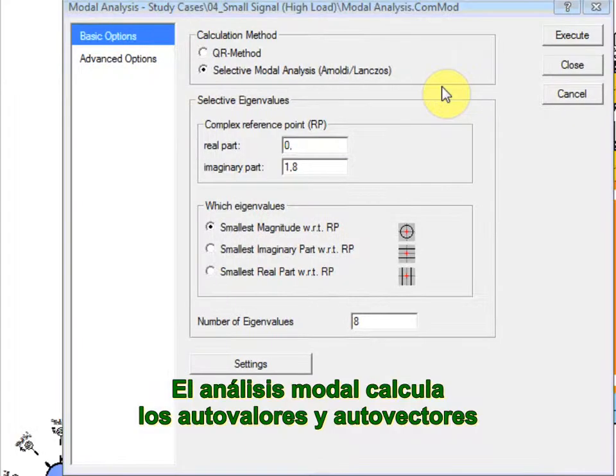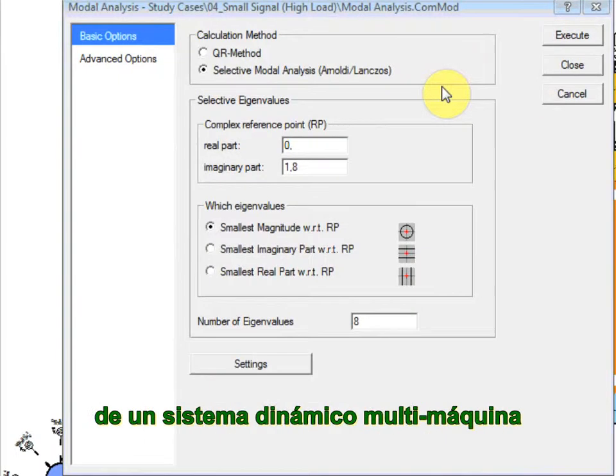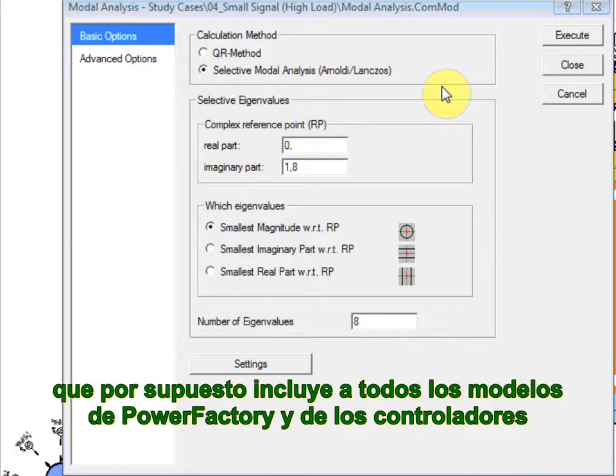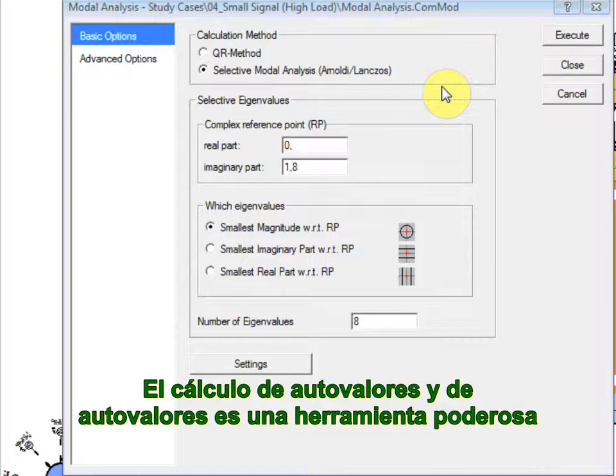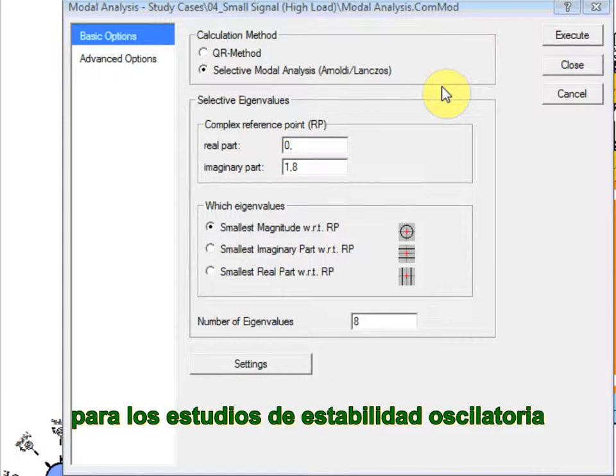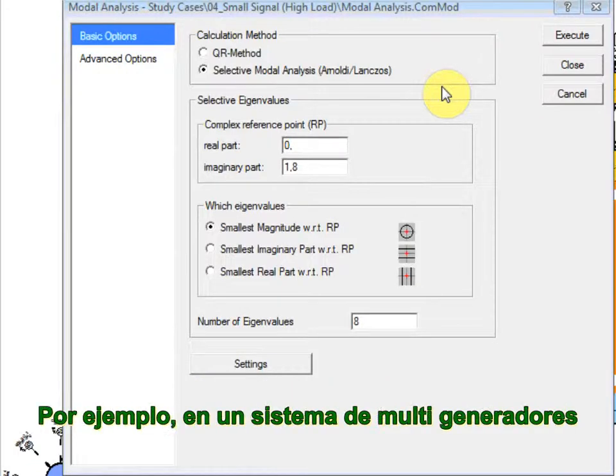The modal analysis calculates the eigenvalues and eigenvectors of a dynamic multi-machine system, including all controllers and power plant models. The calculation of eigenvalues and eigenvectors is the most powerful tool for oscillatory stability studies.